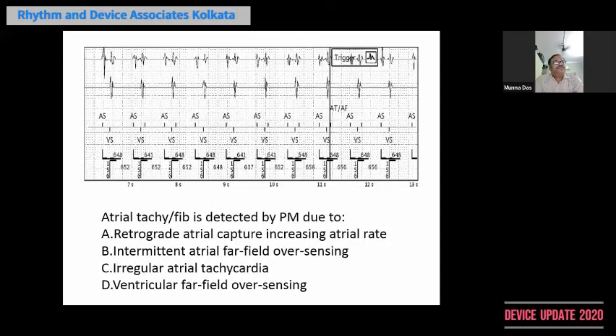So people have said ventricular far field oversensing. Now the correct answer would be ventricular far field oversensing, because if we draw a vertical line on the ventricular EGM, we can find that it is temporally correlated with the second atrial EGM on the atrial channel. Therefore it is the far field ventricular signal that has been wrongly sensed by the atrial channel, and it is counting them in the tachycardia or fibrillation range and diagnosing it as atrial tachyarrhythmia. Now what to do?